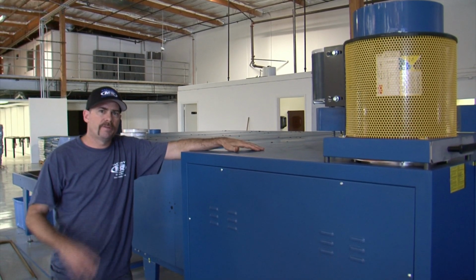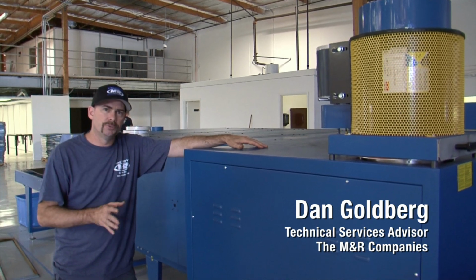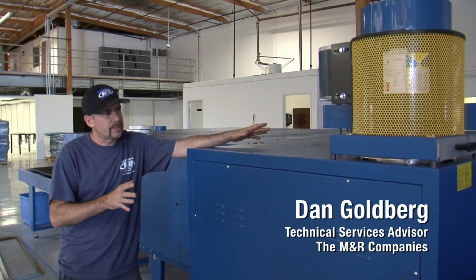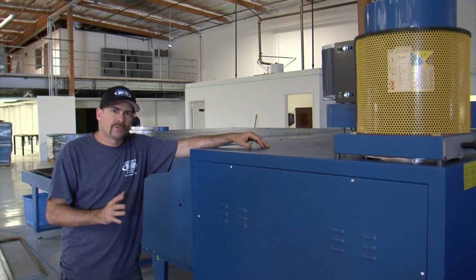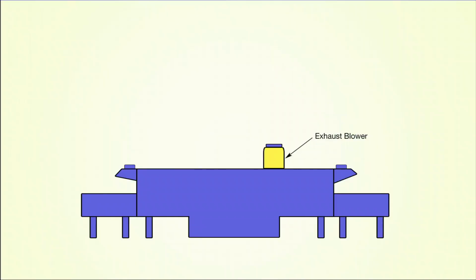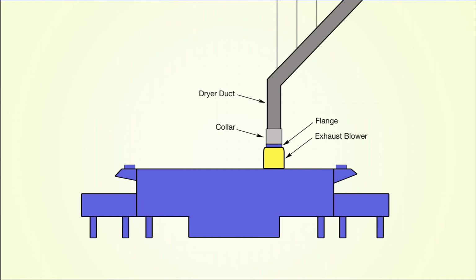M&R dryers have exhaust blowers mounted to them on the top of the unit. This is a Sprint 2000 dryer. We have a 12-inch tubaxial fan exhaust blower on this unit. The plumber will soon connect his ductwork to our flange. He's going to use a collar going around the flange to his first piece of duct, giving me about a 10 to 12-inch gap.